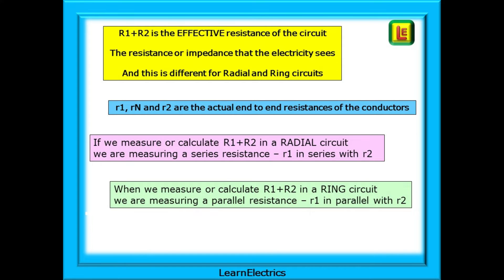If we measure or calculate big R1 plus R2 in a radial circuit, we are measuring a series resistance — R1 is in series with R2, and the effective resistance will increase as the two conductor resistances add together. However, when we measure or calculate big R1 plus R2 in a ring circuit, we are measuring a parallel resistance. Little r1 is in parallel with little r2, and the effective resistance decreases — it becomes smaller.